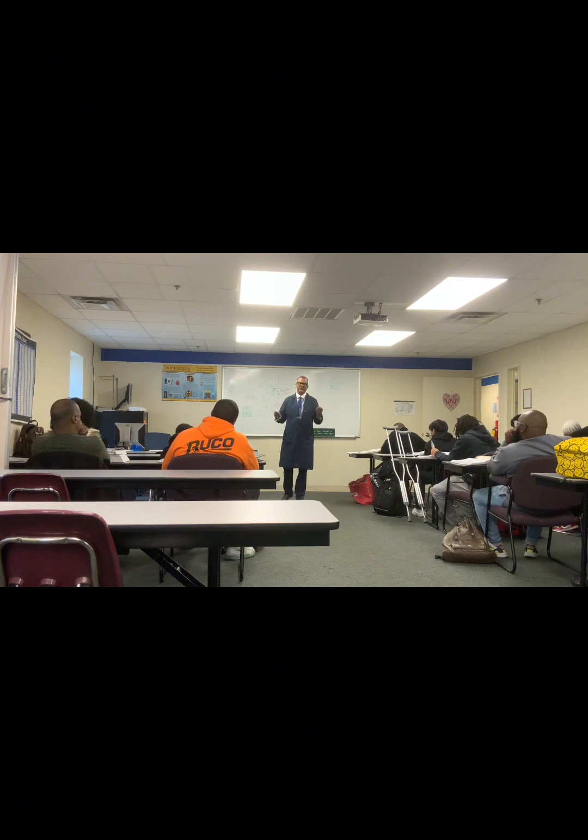So they're so much better than they used to be. The issue is if I get satisfied, meaning I am what? Satisfied means I'm at set point. So if I'm satisfied at that set point, then upstairs, that blade is wide open and it's starting to close. But it's going to close to a minimum. We normally set ours to a minimum of 15%. So some air goes by.